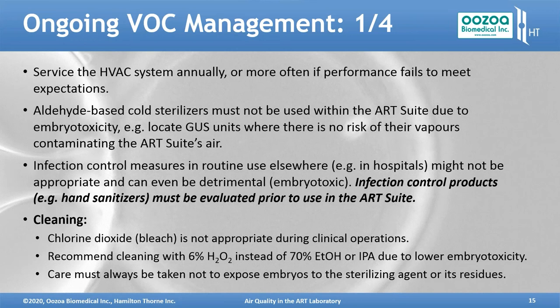In terms of cleaning, chlorine dioxide or bleach is not appropriate during clinical operations. You could use that for your cleans in your downtimes, but it's not the best thing to use when you've got embryos around the place. We recommend cleaning with 6% peroxide rather than alcohol or isopropyl alcohol, because it's much lower embryo toxicity. Care must always be taken not to expose embryos to the sterilizing agent or its residues. Obviously, you don't use things like peroxide to clean culture dishes. They're already sterile. You just want to make sure they don't get into your culture system. But they're perfectly good for cleaning the surfaces because peroxide breaks down to oxygen and water vapor and water, so you don't have any contaminants.